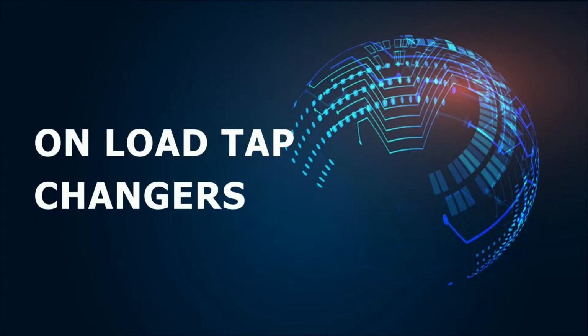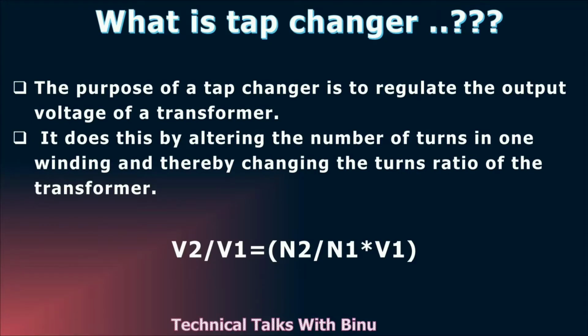Today we are going to discuss on-load tap changers in a transformer. First of all, let's see what a tap changer is. A tap changer is a device which is intended to change the output voltage of a transformer as per the requirement.